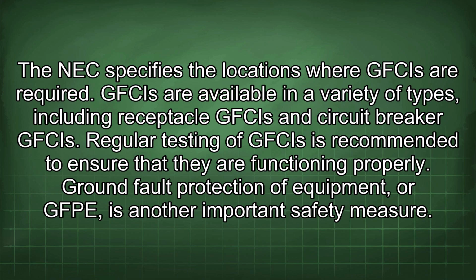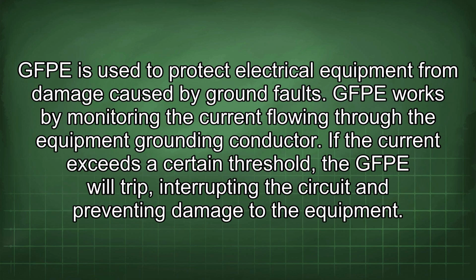Ground fault protection of equipment, or GFPE, is another important safety measure. GFPE is used to protect electrical equipment from damage caused by ground faults. GFPE works by monitoring the current flowing through the equipment grounding conductor. If the current exceeds a certain threshold, the GFPE will trip, interrupting the circuit and preventing damage to the equipment.